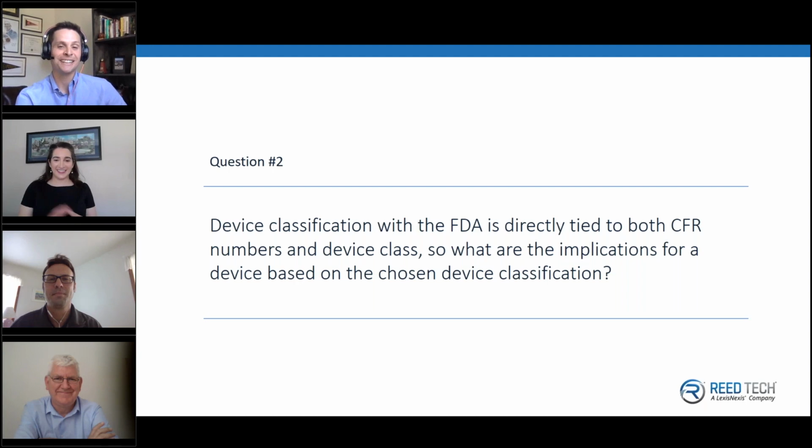No, sorry for cutting you off. I was going to add, there really is a wealth of information there that you touched on. I know I didn't utilize it to its full potential, but in that FDA product code database there are summaries of 510Ks and sometimes even redacted 510Ks where, if you find a similar device, it lays out some of the testing they've maybe done, performance or clinical testing. So it really gives you a good idea, again, going back to getting ahead of things: what type of testing or what type of pathway do I need to start preparing for, knowing it could change, but at least a good starting point.